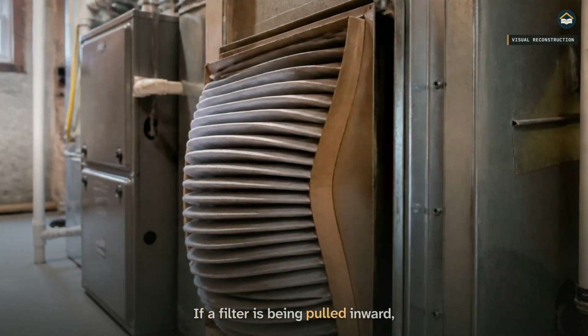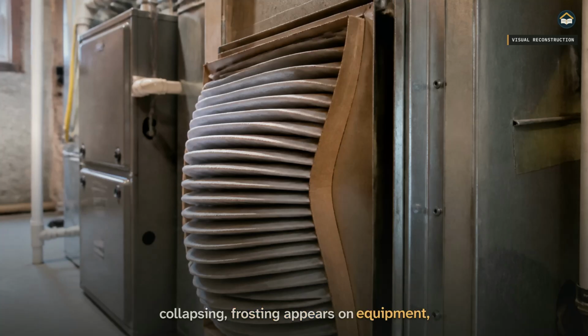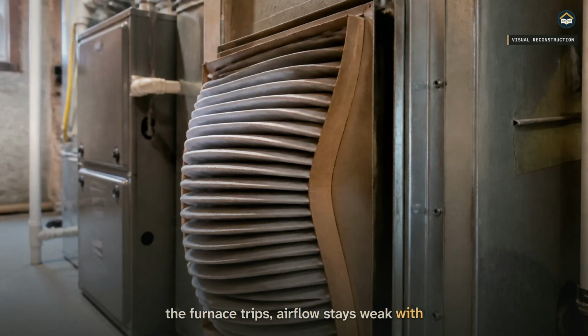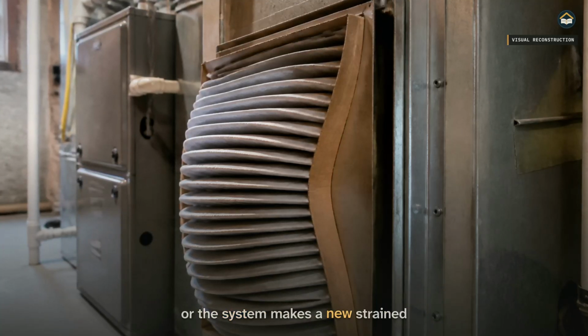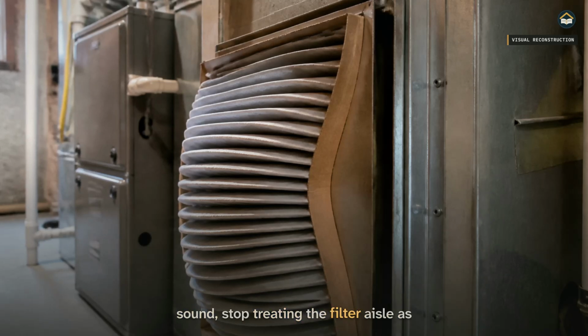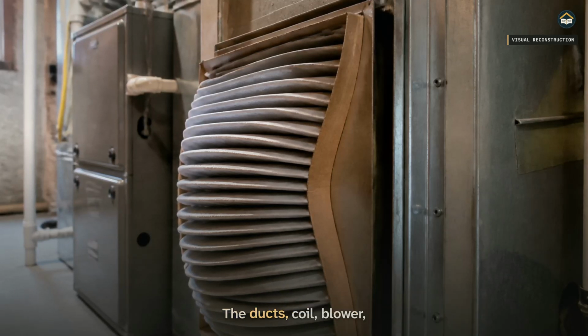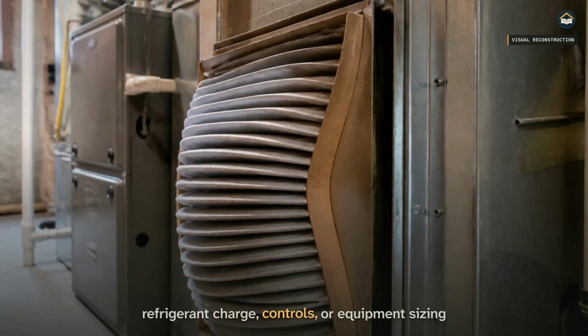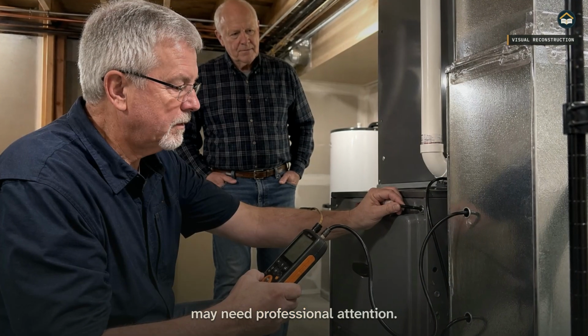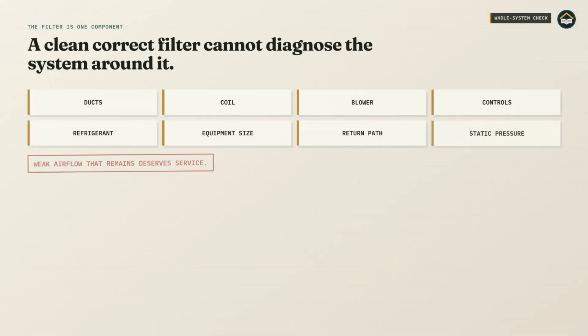If a filter is being pulled inward, collapsing, frosting appears on equipment, the furnace trips, airflow stays weak with a clean correct filter, or the system makes a new strained sound, stop treating the filter aisle as the entire diagnosis. The ducts, coil, blower, refrigerant charge, controls, or equipment sizing may need professional attention. A filter is a maintenance item. It is not a substitute for diagnosing the system around it.